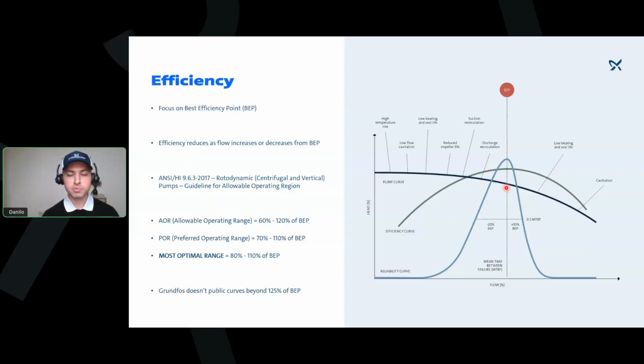The demand in a commercial building is usually not constant. It's not always the same, and it's going to vary. Once you start increasing and reducing your flow, you start getting into trouble if you go too far out of your best efficiency point. As you see in a few examples here, if you run too far to the right side, you start having lower bearing and seal life. On the left side, you can also have low bearing and seal life. If you go too far out, that's when you start getting cavitation. At lower flows, you can not only have cavitation, but also recirculation on the discharge and suction sides of your pump.